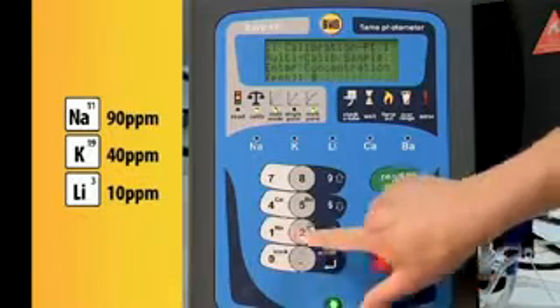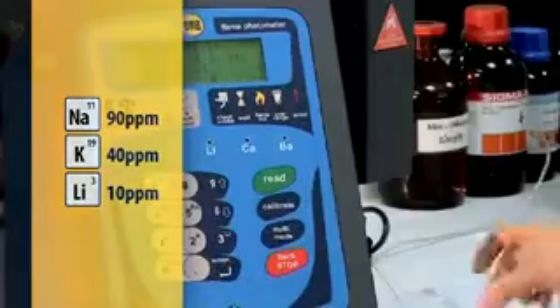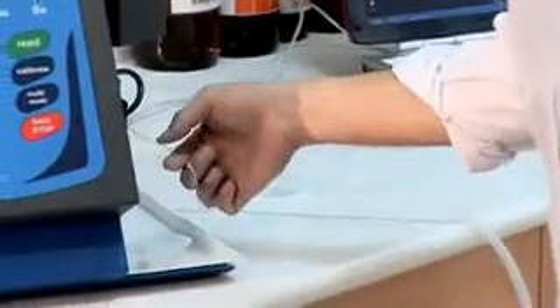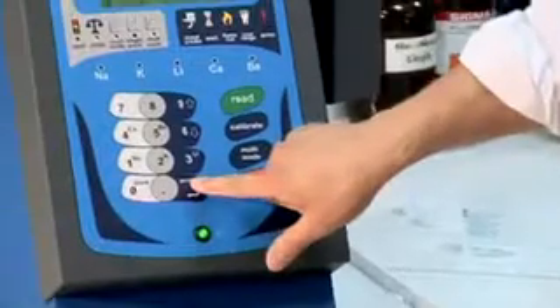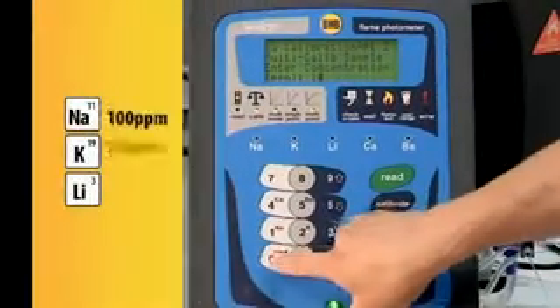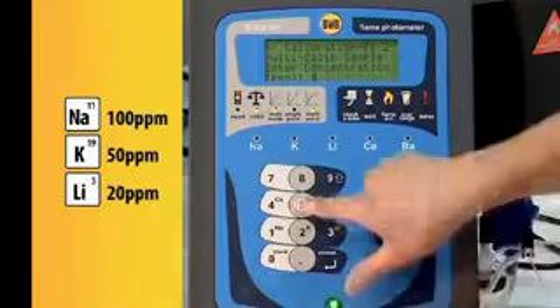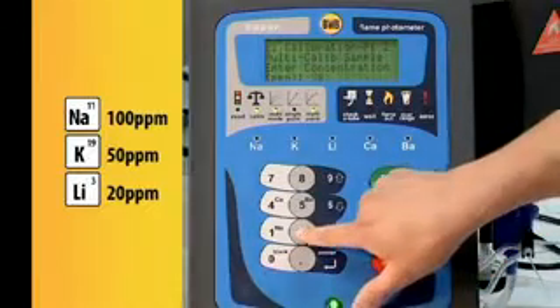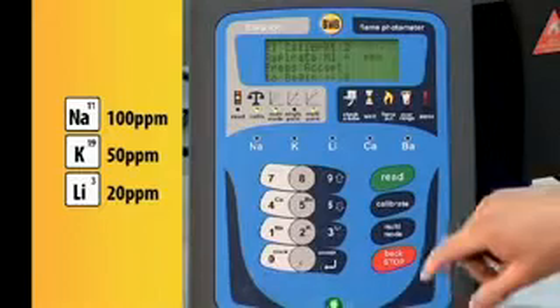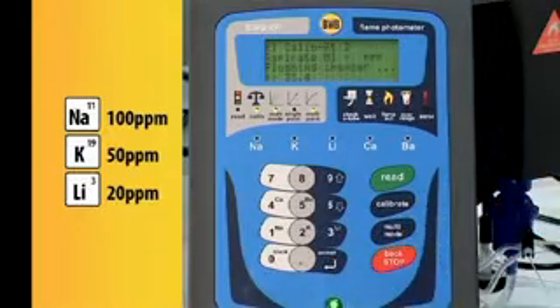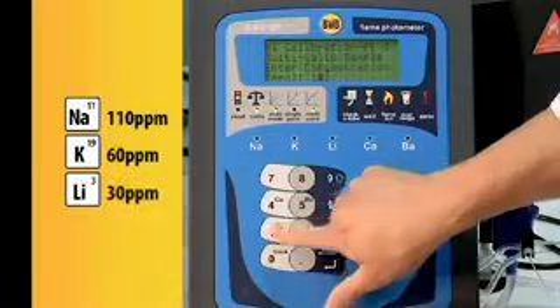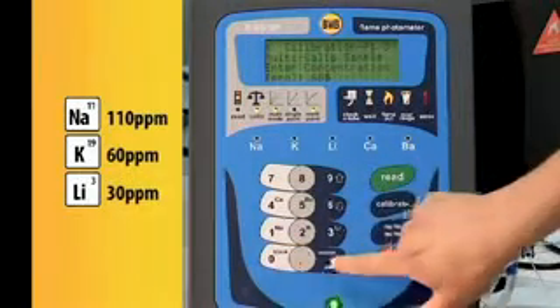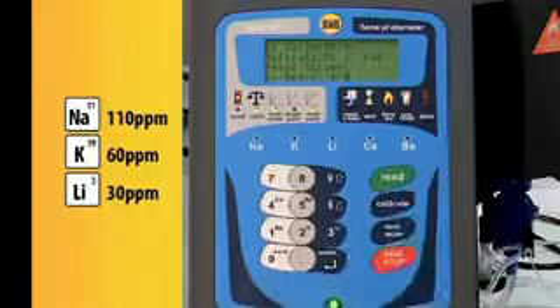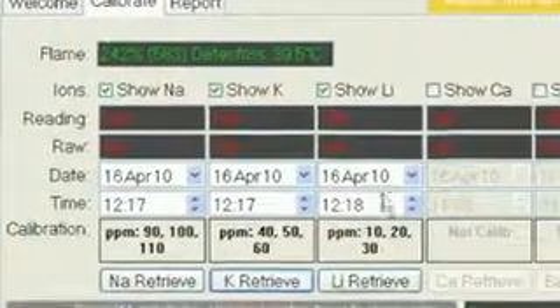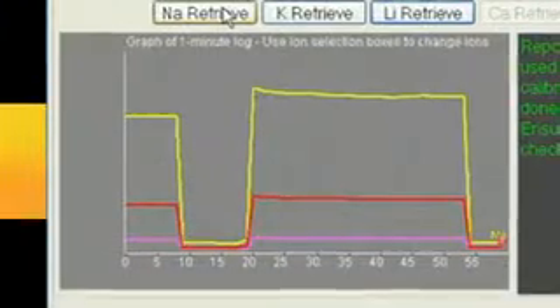We are prompted for a number of points, enter 3. Run the blank as before. We are now prompted for standard 1, sodium, enter 90. Potassium, enter 40. And lithium, enter 10. Aspirate standard 1 and key accept. We are now prompted for standard 2. Enter 100 for sodium, 50 for potassium and 20 for lithium.